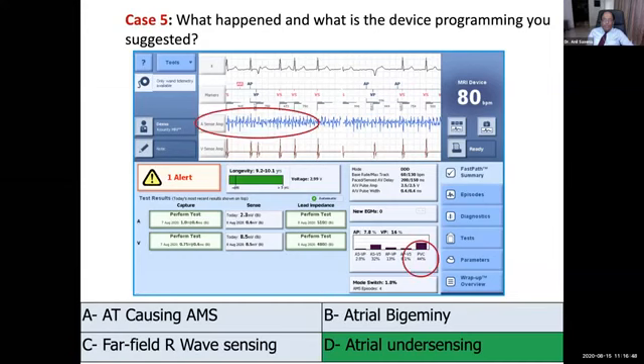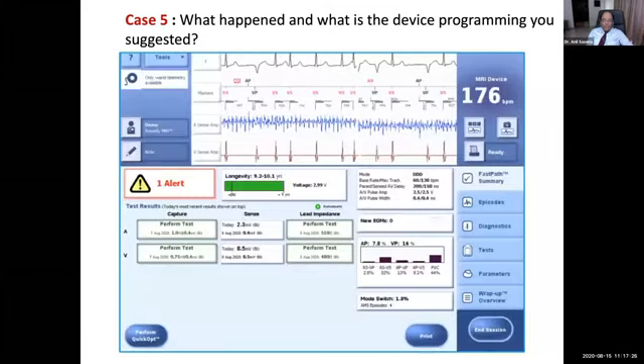That also causes one more problem, which is the PVC response. The PVC count is being shown as 44%. Now, this may not be so, because as I told you earlier, if there is a V sense without any atrial activity, it will be counted as a PVC. So because the atrial channel is not showing any sensing, the pacemaker senses all these as PVCs. So the PVC count becomes high. So that's another problem.